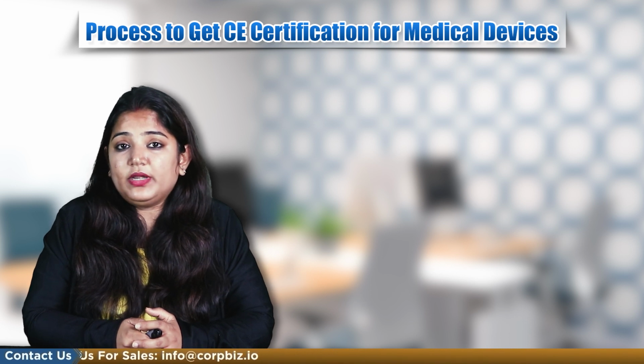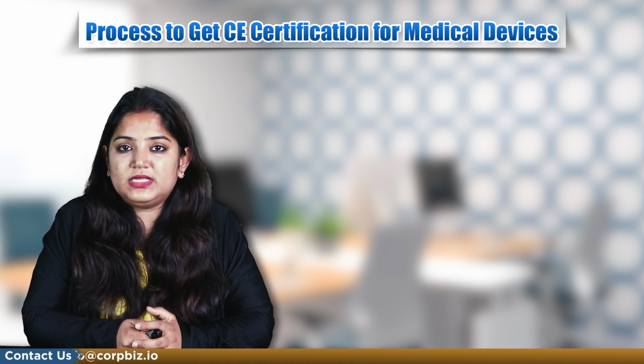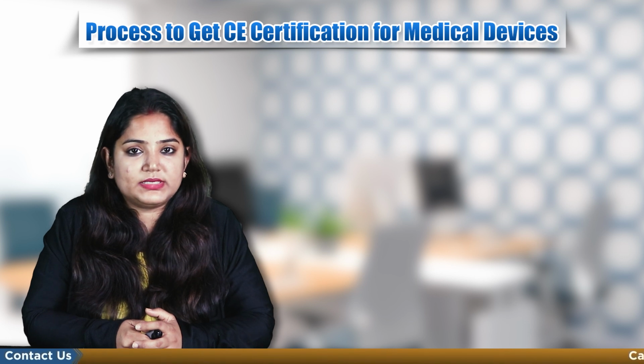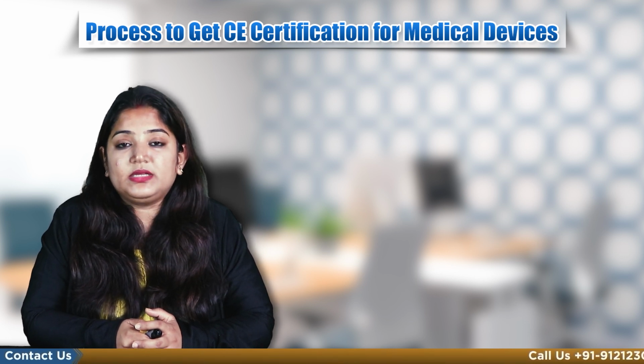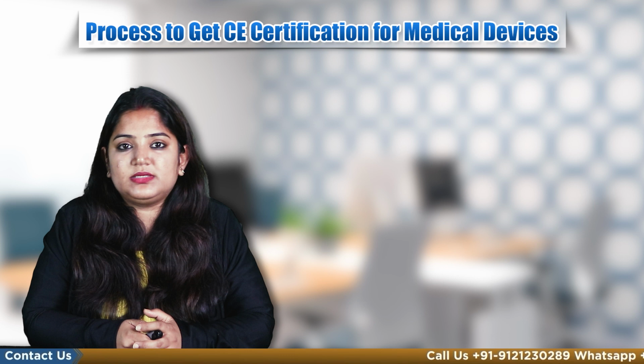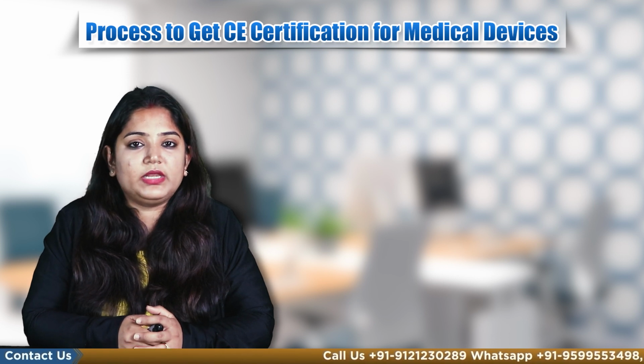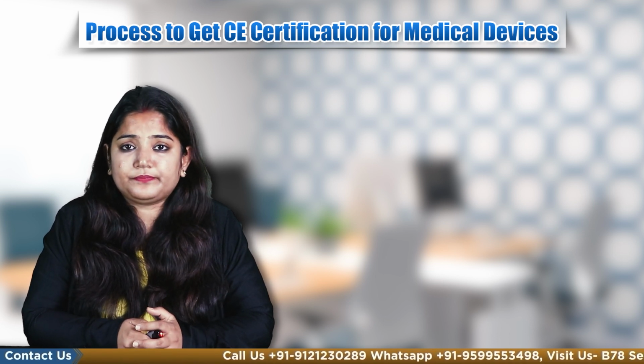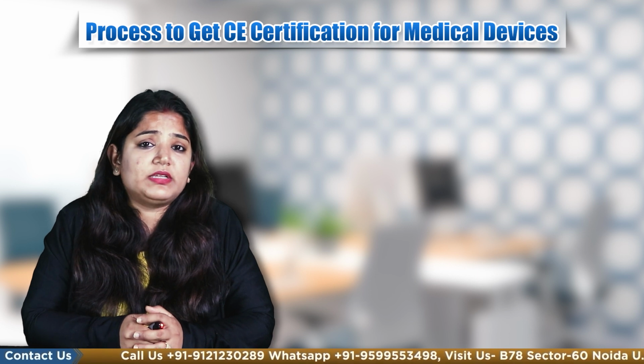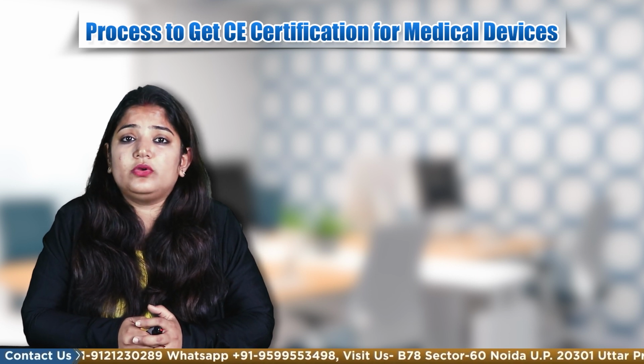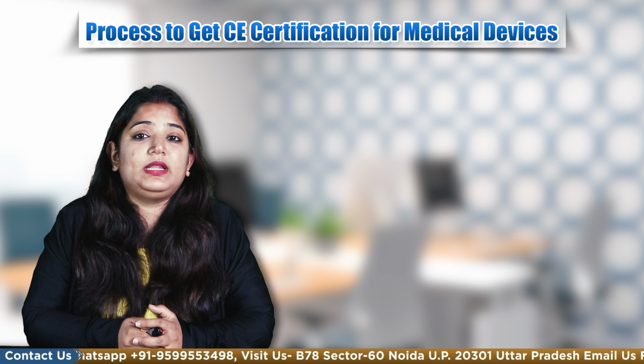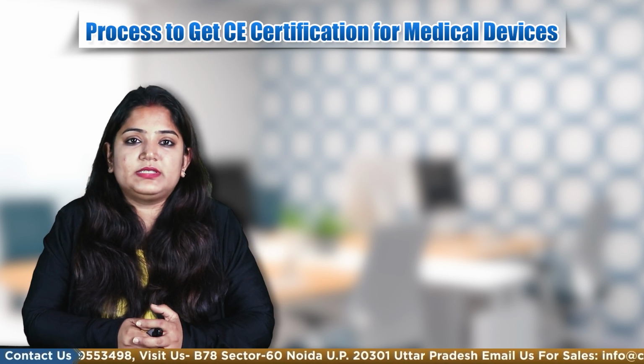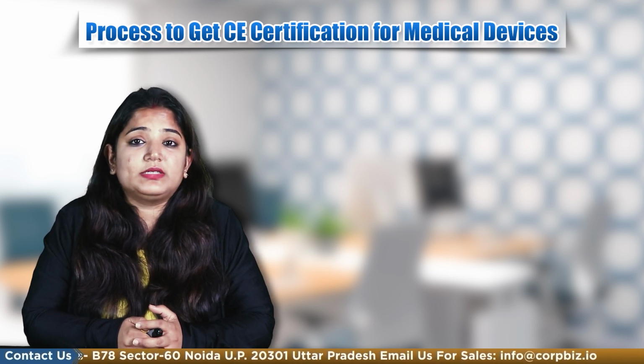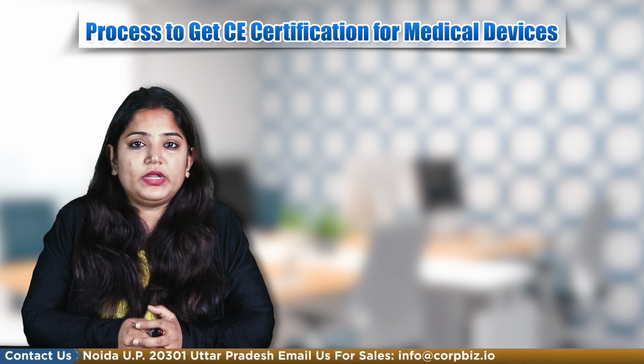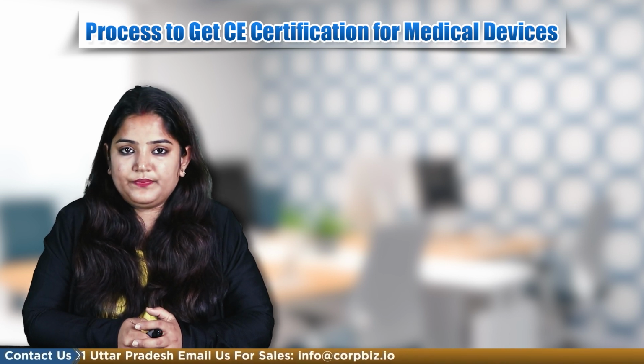A notified body is an EU-recognized agency that can perform the assessment of conformity concerning medical devices in view of underlying regulatory standards. Once the manufacturer successfully undergoes the auditing requirements, declares conformity, and affixes CE marking, their products become eligible to be sold across the European market.